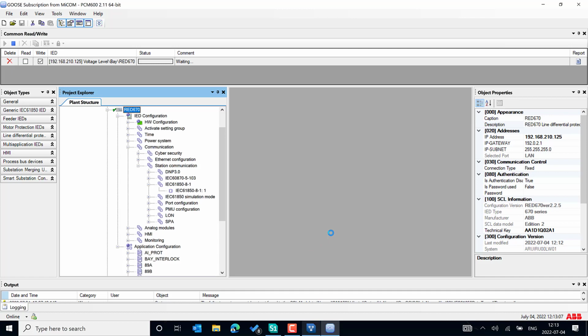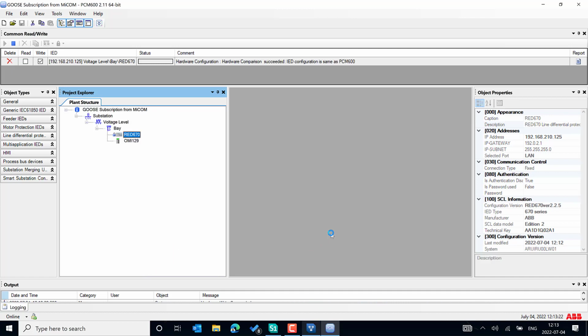What I can do is use IEDScout to make sure that even if you have a real IED as a GOOSE publisher, in some cases you may have a problem. Maybe you followed the first step and you wanted to make sure you did the proper engineering. If you want to find out the root cause, why it's not exactly publishing properly in the real network, then you can use IEDScout in that case to find exactly where the problem is, or you can easily find the solution by simulating the GOOSE control block with IEDScout in a quick time.